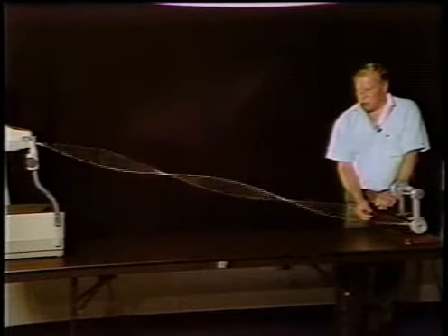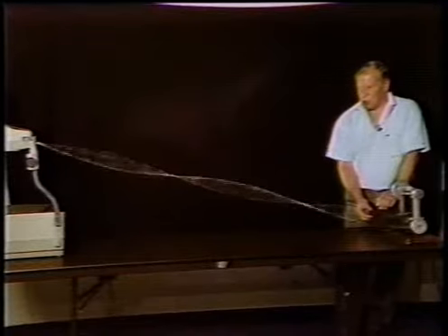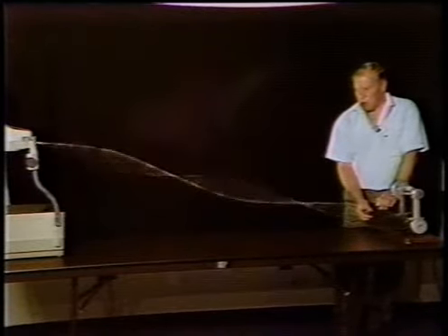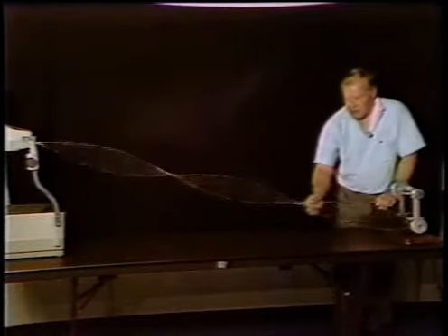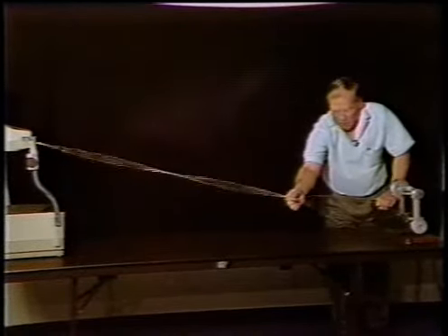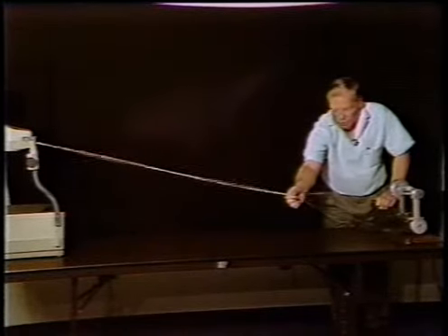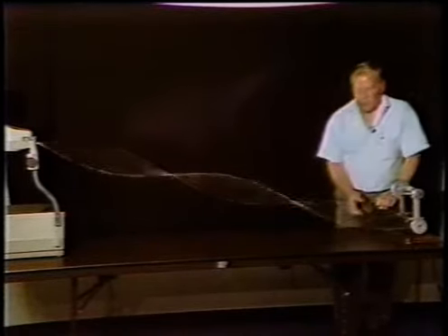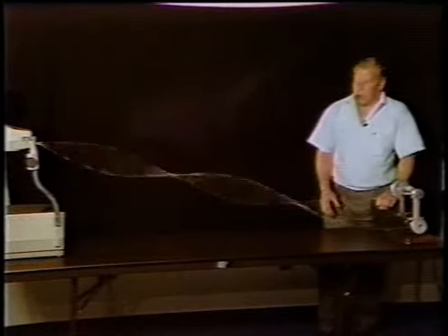Now, we have the exciting force frequency coincident with what is called the third bending mode of resonance. And again, you'll see that the system has broken itself now up into 3 separate spring mass systems, again separated by these points of minimal vibration. Those are referred to as nodal points.